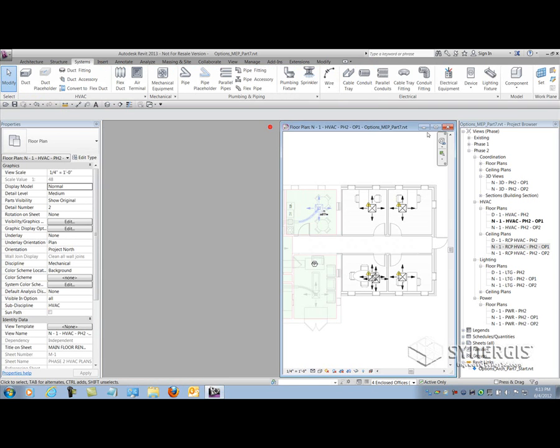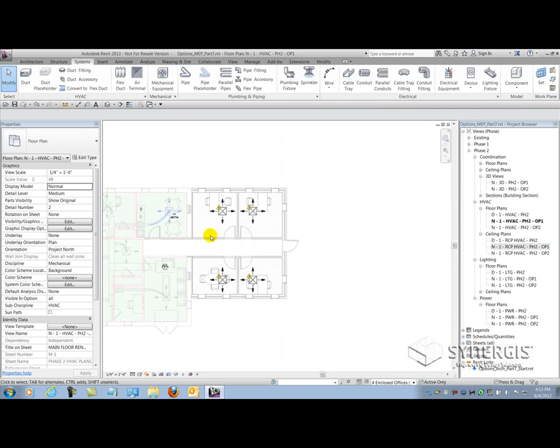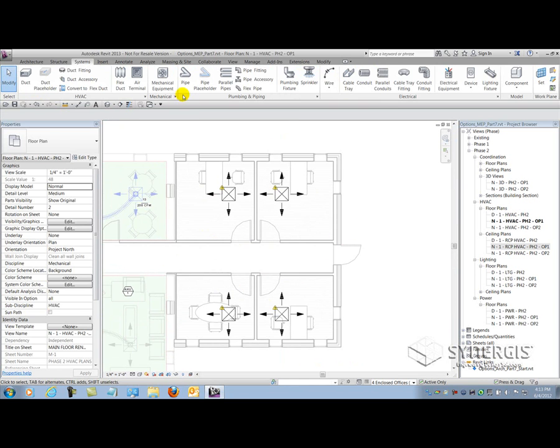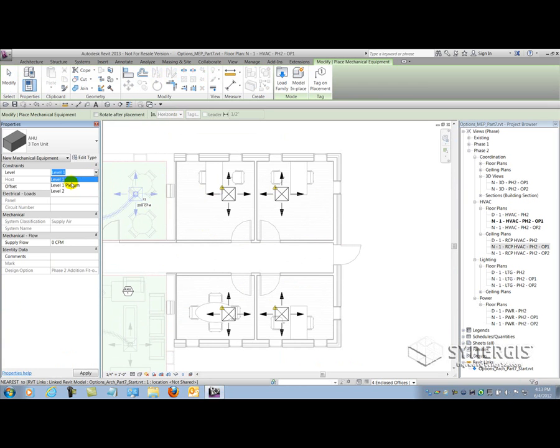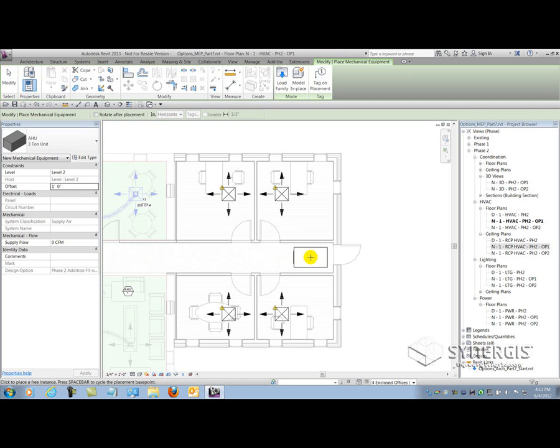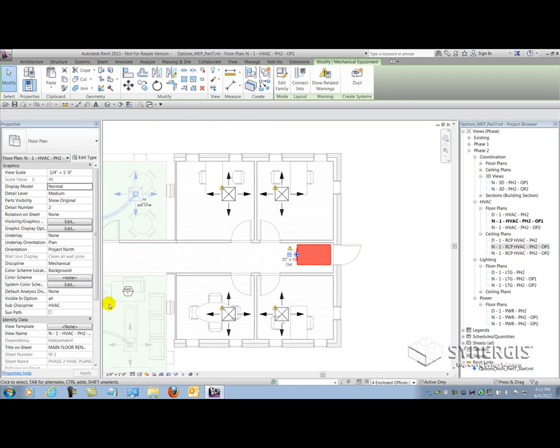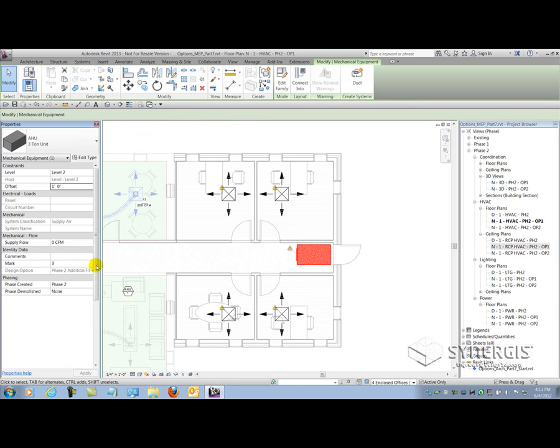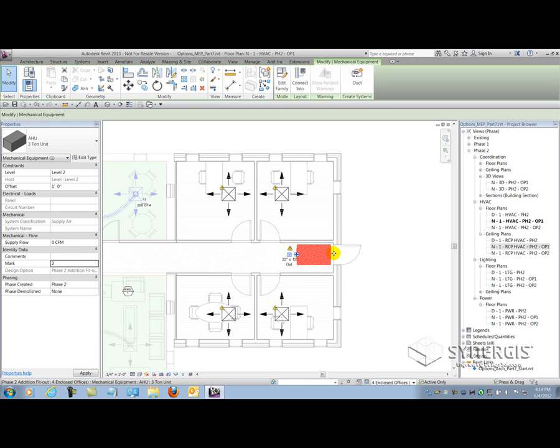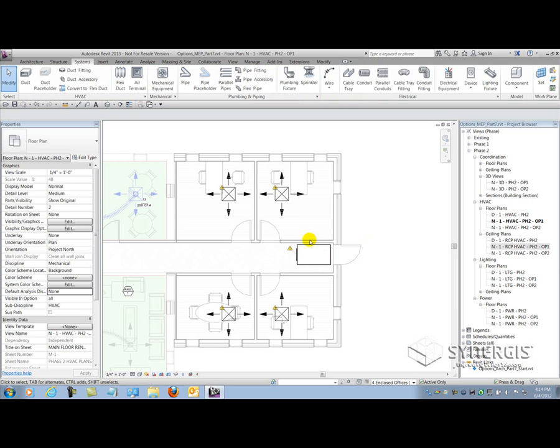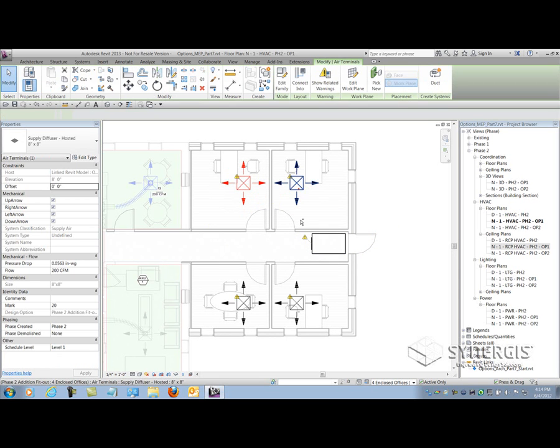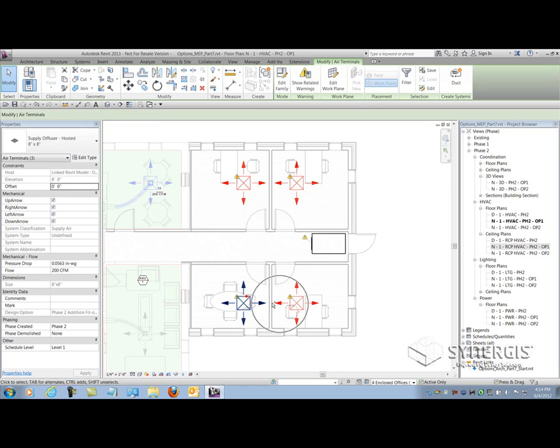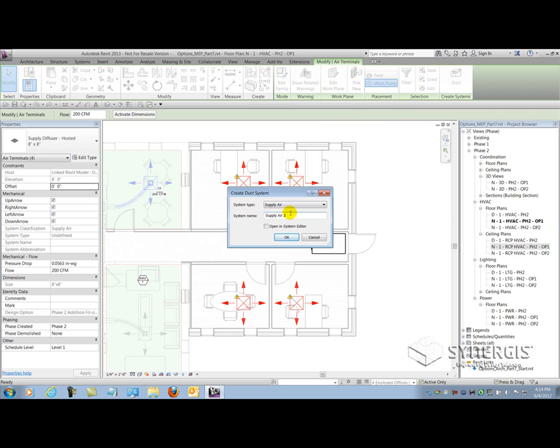Now that I got my air terminals located in my ceiling plan, I can close that down and now I can go place my equipment. To place my equipment just like I would in a new construction project, I'll go pick the mechanical equipment command, set my associated level and my offset if necessary, place the equipment where I want it and then I'm done. Just like I said with the furniture in the architectural model, duplication of elements is not very problematic inside of design options because each option is treated differently. If I have two units called number two, even though they're in the exact same spot in both options, Revit still identifies them as unique instances.